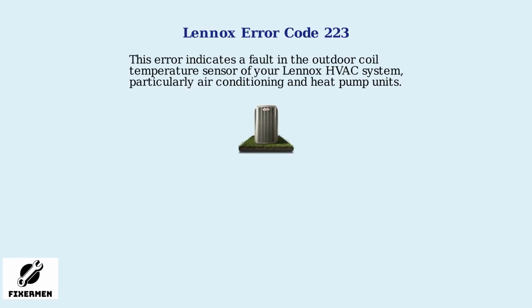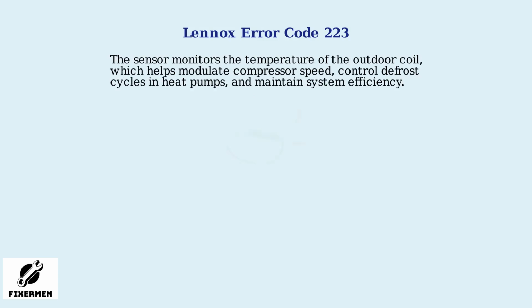Lennox Error Code 223 indicates a fault in the outdoor coil temperature sensor, which is a critical component in your Lennox HVAC system. This primarily affects air conditioning and heat pump units. This sensor monitors the temperature of the outdoor coil, which is essential for modulating compressor speed, controlling defrost cycles in heat pumps, and ensuring overall system efficiency, especially in variable capacity units. When this sensor malfunctions, it can lead to inefficient cooling or heating or even system shutdown.